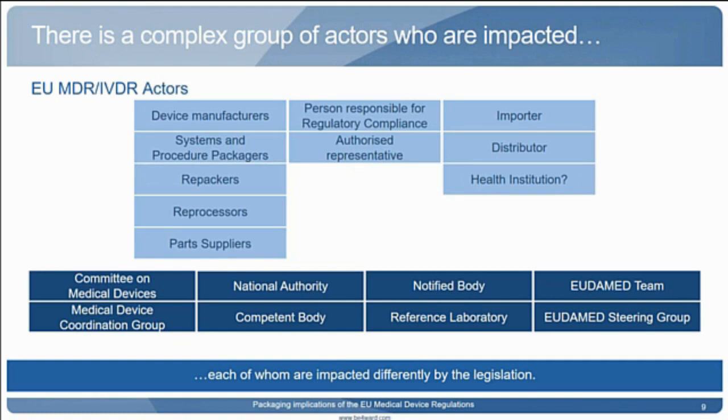In the middle of the slide, you've then got a statement which is the person responsible for regulatory compliance. So anyone who's supplying medical devices will need to have a person who is responsible for the regulatory compliance of those products. Now, that doesn't need to be a full-time employee, but it needs to be a service that's provided and is similar in some ways to a qualified person within the pharmaceutical industry.